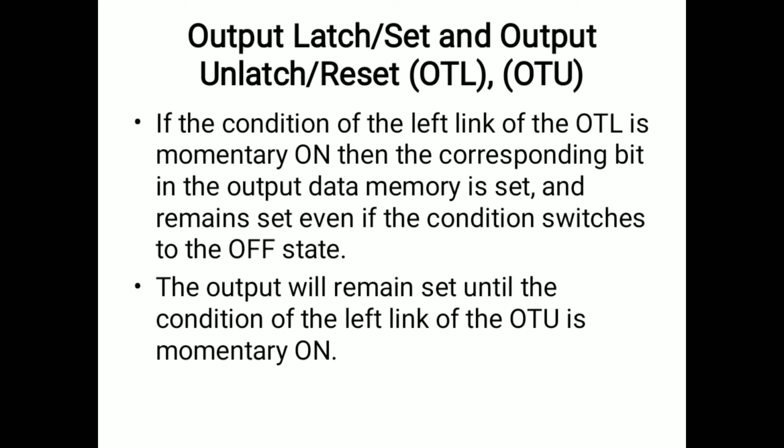Latch means if the input condition on the left link of OTL is momentarily on, meaning for some moments it is on, then the corresponding bit of the output data memory will be set, and it will remain set even if the condition switches to the off state. If a switch momentarily becomes on, then the output will be set to 1 and it will remain 1 even if we open that switch. That is called the output latch condition.